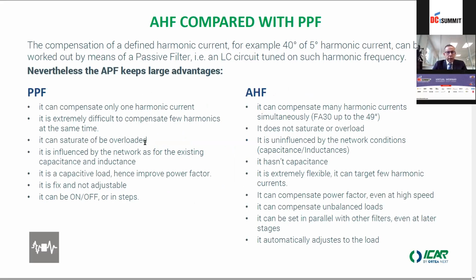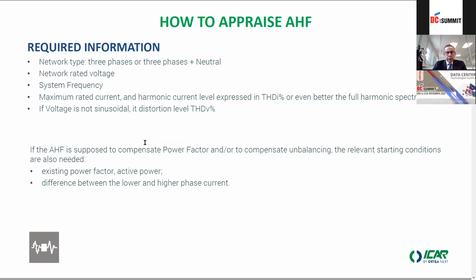So here, let's avoid these parts. When you have troubles on the line and you have high harmonics, you have to measure your THDI and THDV, which are very important points to measure to make a good selection of your harmonic filter.